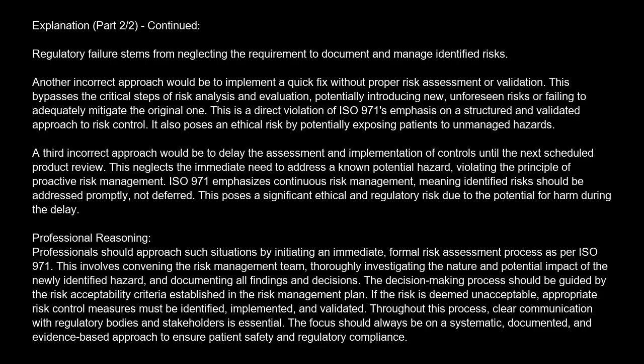The decision-making process should be guided by the risk acceptability criteria established in the risk management plan. If the risk is deemed unacceptable, appropriate risk control measures must be identified, implemented, and validated. Throughout this process, clear communication with regulatory bodies and stakeholders is essential. The focus should always be on a systematic, documented, and evidence-based approach to ensure patient safety and regulatory compliance.